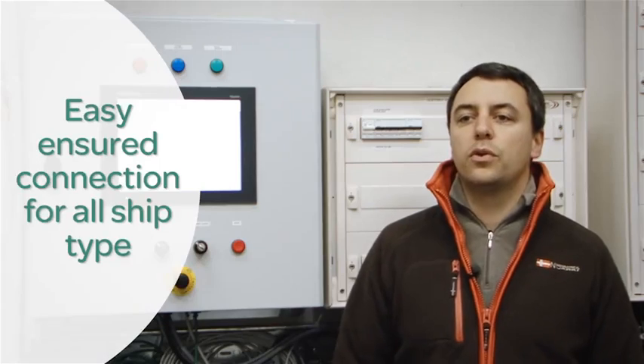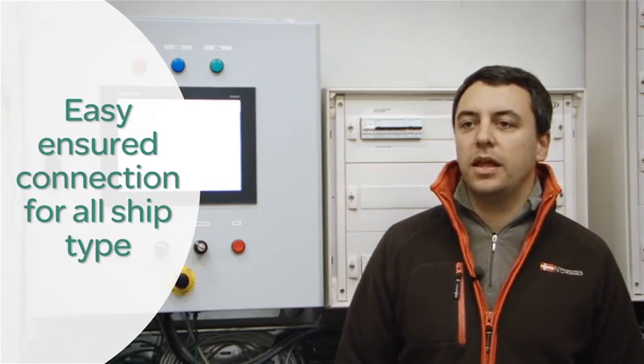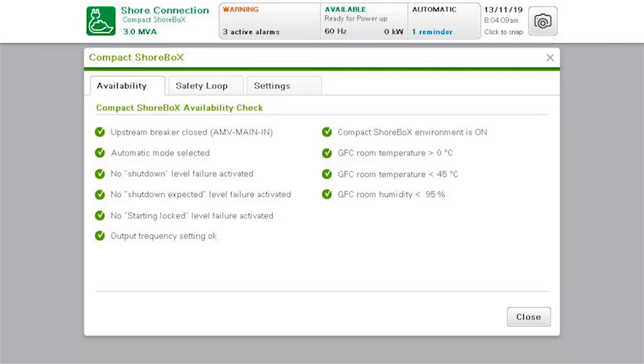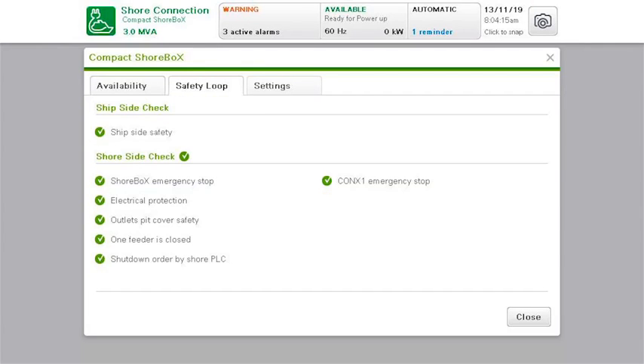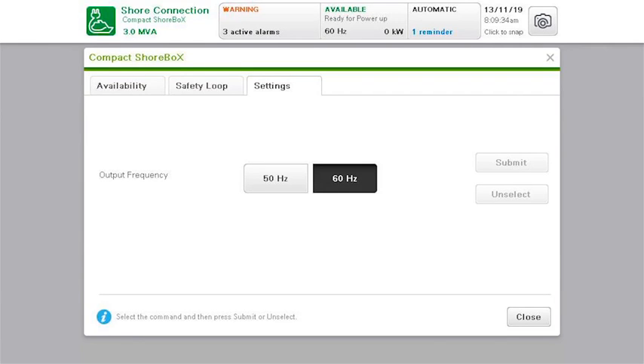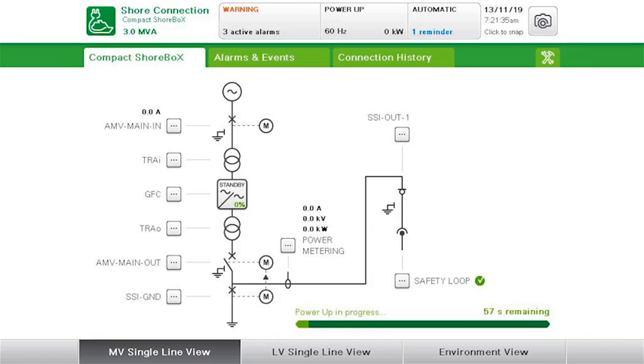Connecting a ship to the grid through the compact ShoreBoX system is pretty simple, and everything can be managed through the HMI. The first step consists in checking availability of the system, as well as the status of the safety loop. Then, regarding information provided by the ship, frequency shall be set up on the HMI through a specific dedicated command. As soon as all elements are ready, including cable connection, the automatic connection can be started from the push button. The connection procedure includes 5 main steps.